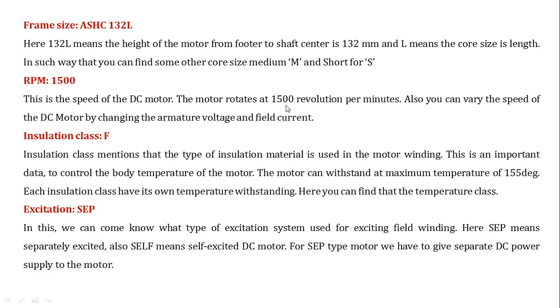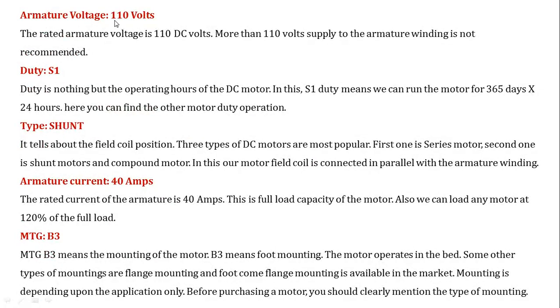The motor rotates at 1500 revolutions per minute. Also, you can vary the speed of the motor by changing the armature voltage and field current. Then the next one is the insulation class, then excitation. Then the armature voltage means how much armature voltage is required to operate that motor. Then the duty cycle. Then the type, whether it is shunt or series. Then the armature current tells us about the rated current of the armature coil. Then MTG means mounting of the motor. B3 means foot mounting.